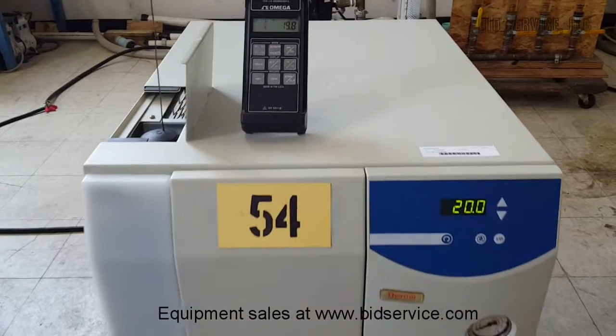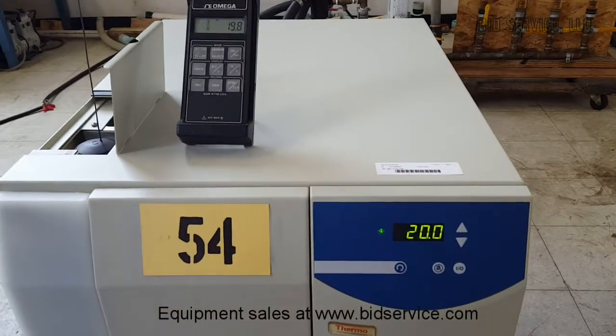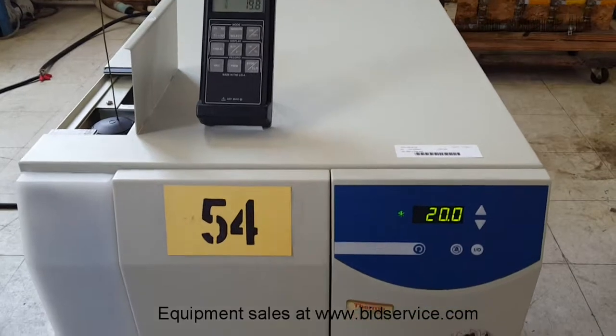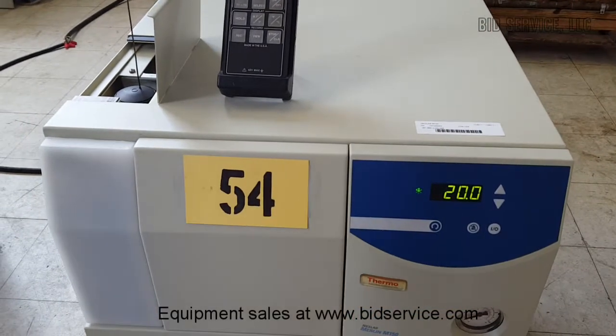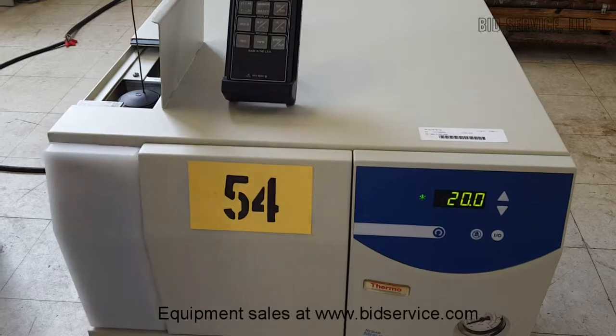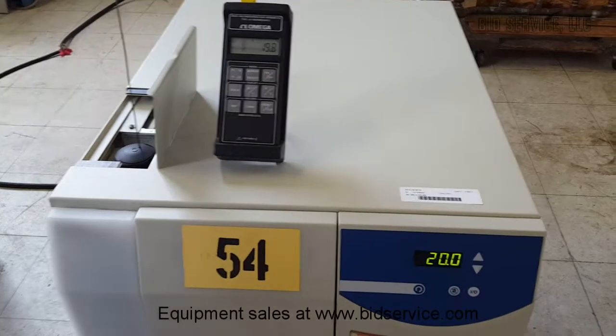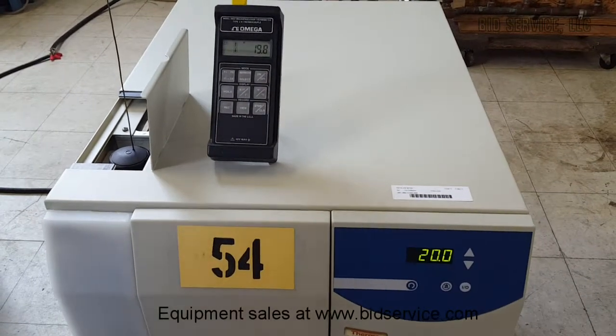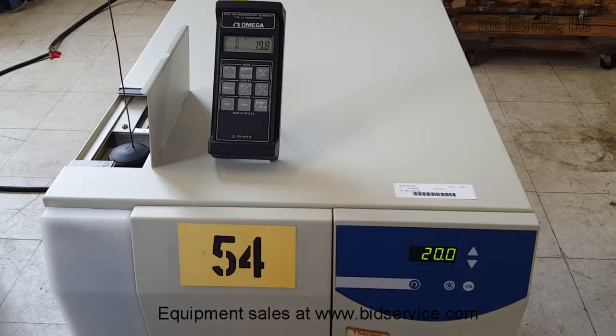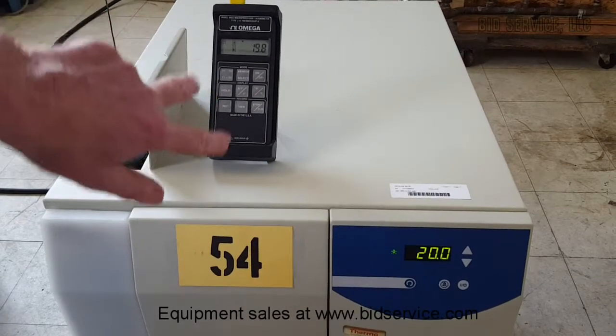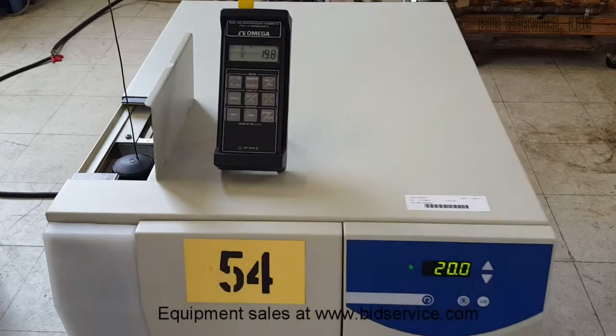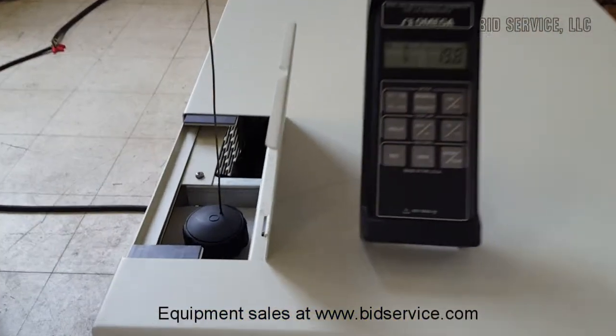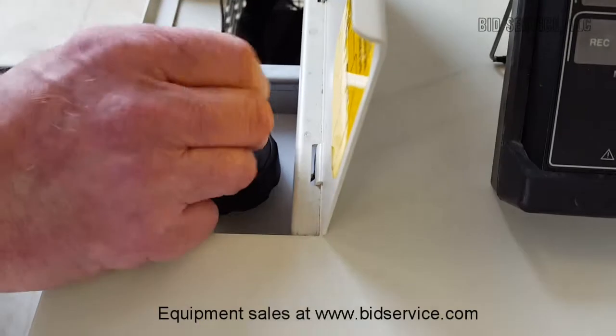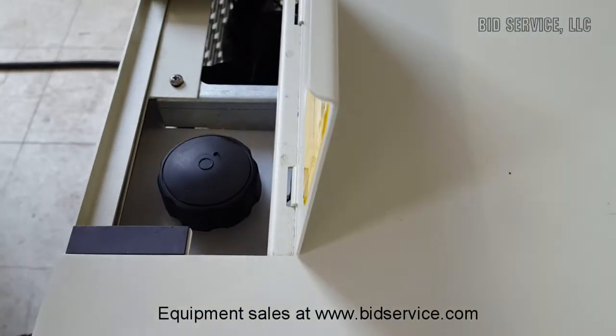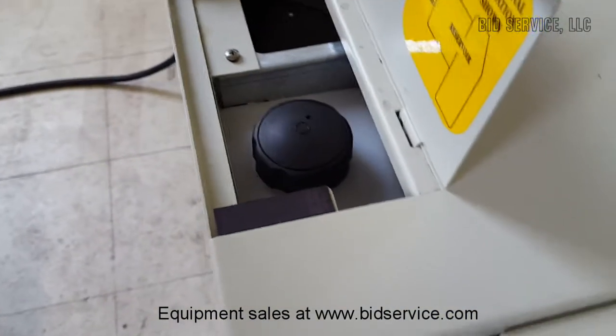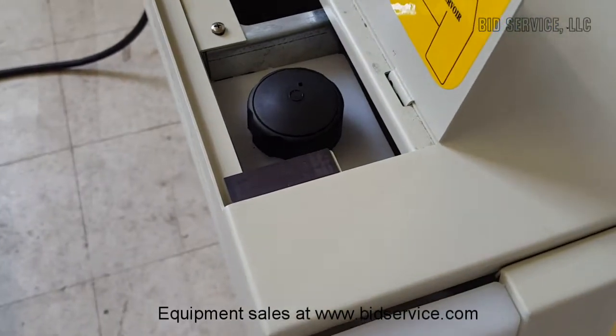I'd like to point out a couple of really nice features about this. Whenever we service and refurbish chillers, we always use a calibrated temperature probe to check the temperature, both up and down, and as you can see, it is virtually almost perfect. What's nice about this one is, if you look closely, they've put a really nice little hole here that allows you to check the temperature without removing the plug.